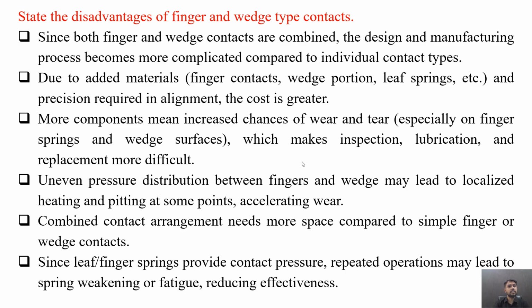The disadvantages of finger and wedge type contacts. So there are several disadvantages of this type of contact. Since both the finger and wedge contacts are combined, the design and manufacturing process becomes more complicated compared to individual contact types. Due to the added materials, that is finger contacts, wedge portion, leaf spring, etc., and the precision required in alignment, the cost is higher.